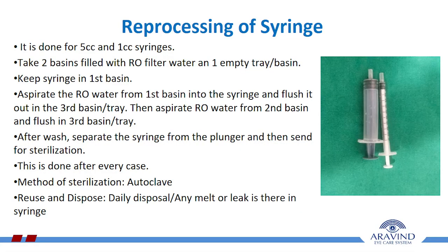Reprocessing of a syringe. It is done for 5 cc and 1 cc syringes. Take 2 basins filled with RO filter water and an empty tray or basin. Keep syringe in the first basin. Aspirate RO water from first basin into the syringe and flush it out in the third basin or tray. Then aspirate RO water from the second basin and flush in the third basin or tray. After wash, separate the syringe from the plunger and send for sterilization. This is done after every case. Method of sterilization is autoclave. Reuse and disposal is a daily disposal, or if there is any melt or leak in the syringe.